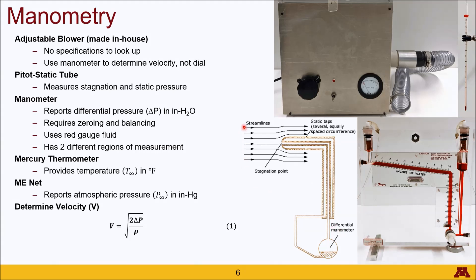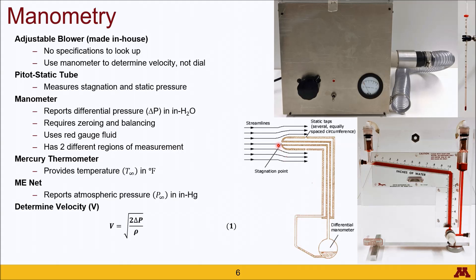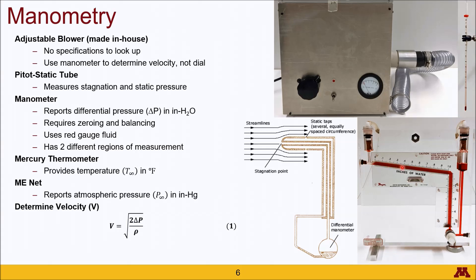The pitot-static tube operates by having the tube placed within the airstream where the stagnation point enters through the tube directly, whereas on the sides of the pitot-static tube are ports that allow the static pressure to be measured. From there, the static pressure follows a line to one side of the differential manometer and the stagnation pressure goes down the middle of the pitot-static tube to the other side of the differential manometer. As velocity increases, the red fluid traverses to the right and gives you a pressure reading in inches of water.